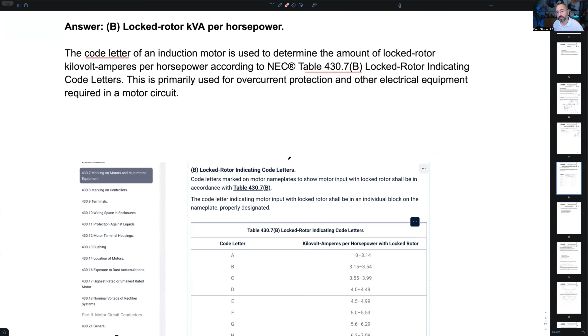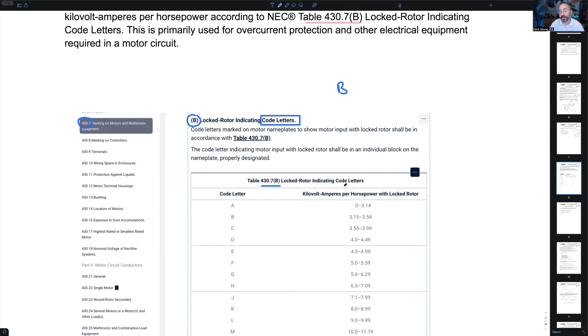We go to 430.7. (B) is the locked rotor indicating code letter, there it is. That code letter, you'll see it stamped on the nameplate. You'll just see a letter. Say we had the letter B stamped on it. It's not NEMA design B. It's code letter B. It's the letter that corresponds to this table, 430.7(B), the locked rotor indicating code letter.